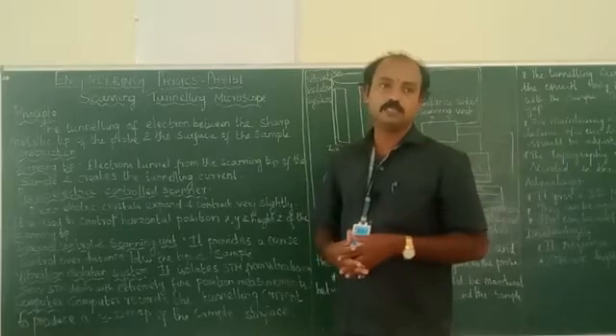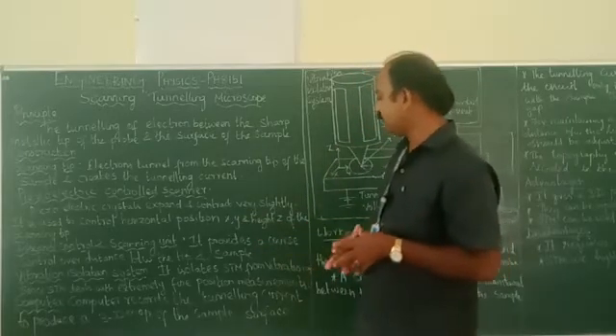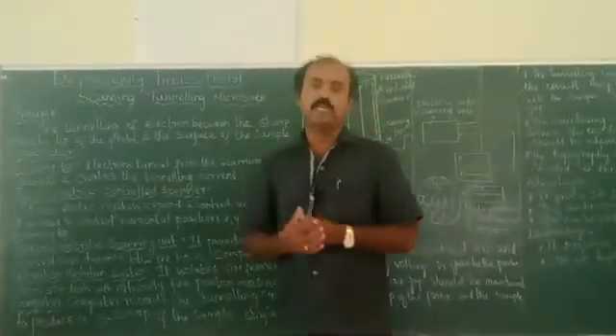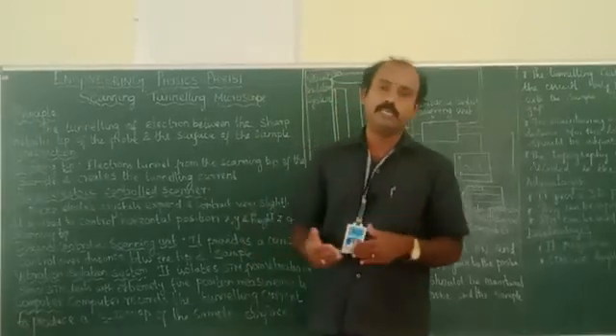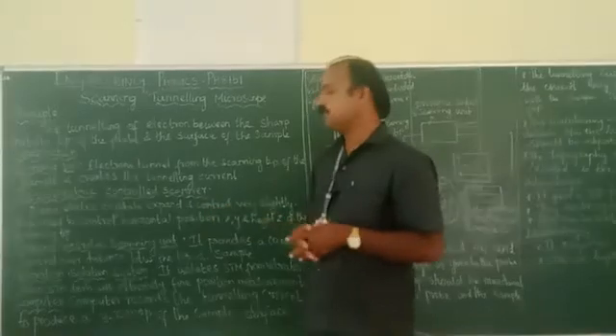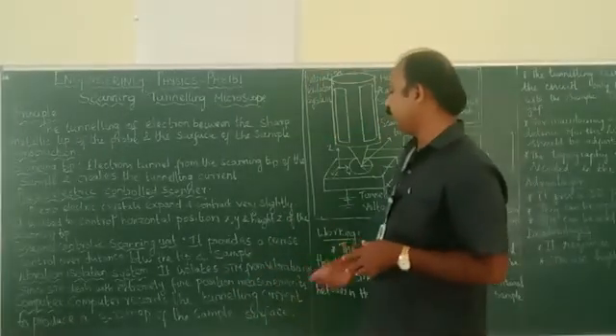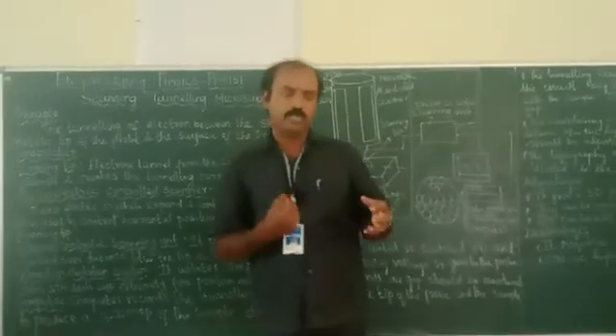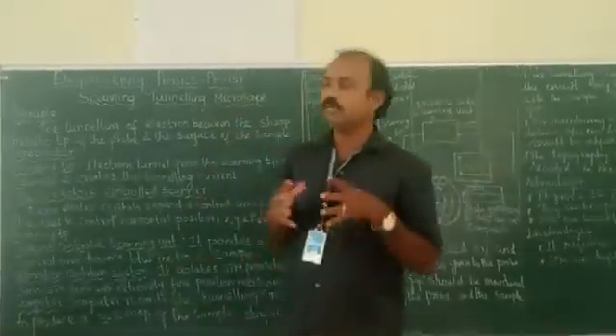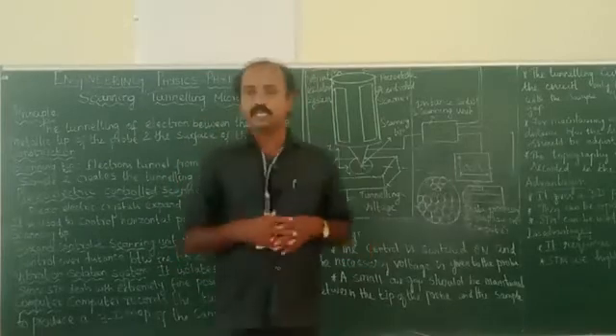The other component used here is the computer, which records the tunneling current. The amount of electron entering from the tip of the probe to the surface produces the tunneling current. The corresponding tunneling current is measured and the information is stored in the computer. The computer records the tunneling current to produce a three-dimensional map of the sample based on the output current received from the probe.